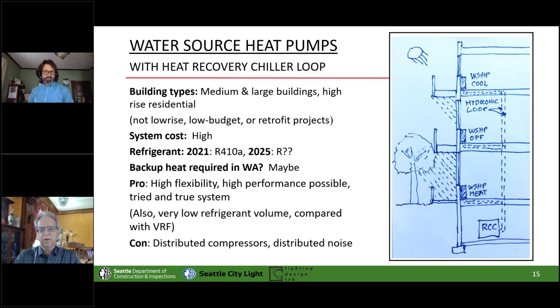Well, also, the refrigerant itself in these very tiny quantities, as things leak, like grocery stores are notorious, they lose huge amounts of refrigerant into the grocery store. But it's not especially a health hazard or a danger in itself at those little units. And in fact, the bulk of the problem is in catastrophic leaks where something breaks and everything dumps out. The bulk of the problem for building occupants. However, those little pinhole leaks existing everywhere in the world add up to a real global warming thing too.